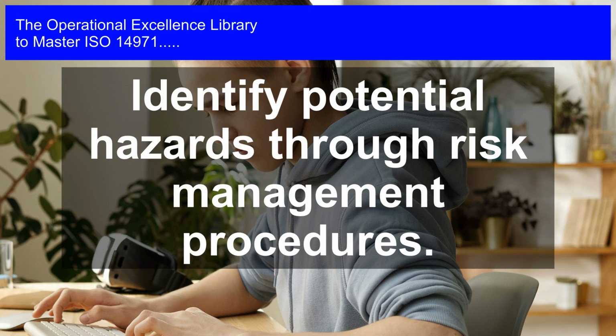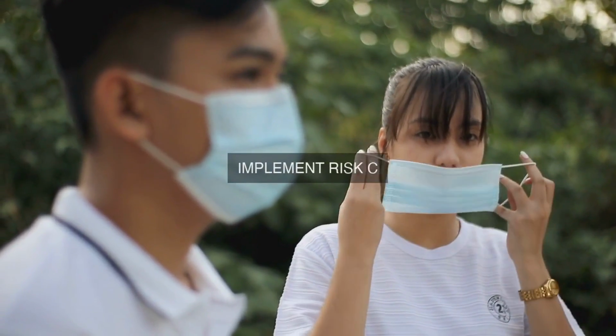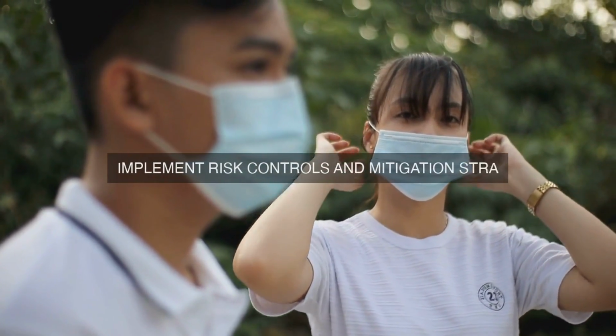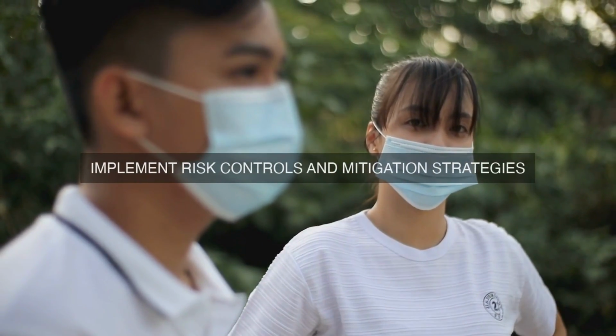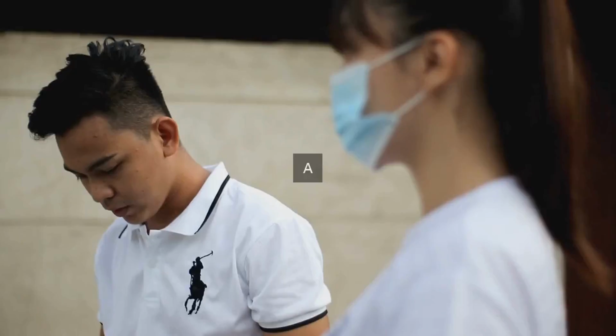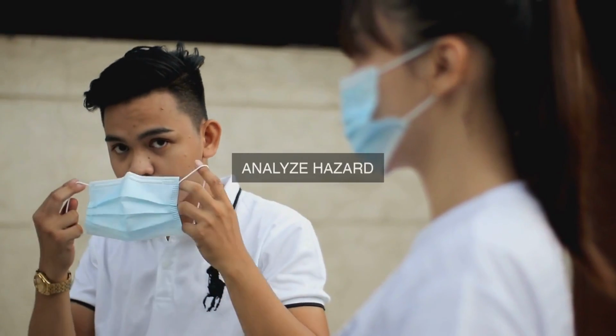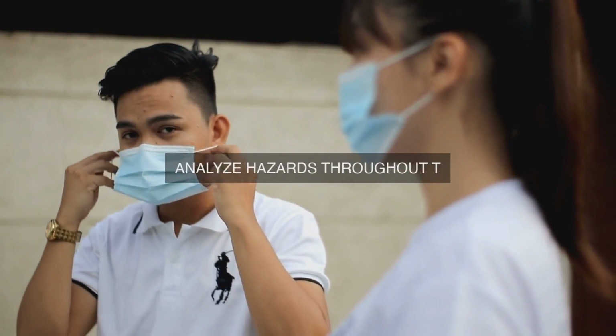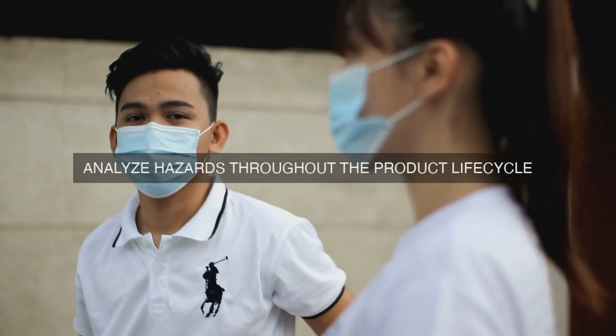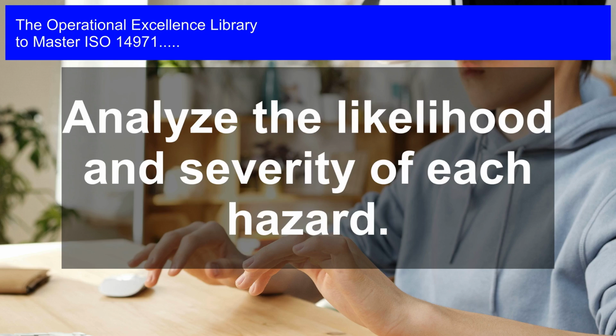According to ISO 14971, risk management involves a series of iterative and interrelated activities, including risk analysis, risk evaluation, risk control, and risk reviews. The standard defines risk as a measure of the probability and severity of harm or damage to people, property, or the environment. Hazards, on the other hand, are defined as potential sources of harm.